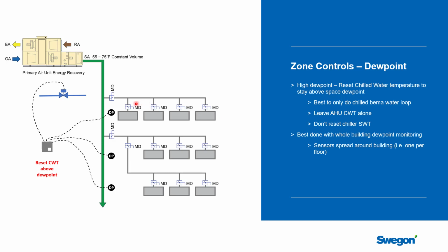that humidity will quickly spread across the whole floor, and so you can get away with having just one sensor per floor and monitor, using your building automation system, the overall dew point of the building floor by floor. Or if you had a large building, you might put a couple of sensors per floor at strategic locations, and if any one of these is getting close to the dew point limit, use that signal to reset the chilled water. So it's a nice way to be able to do that.